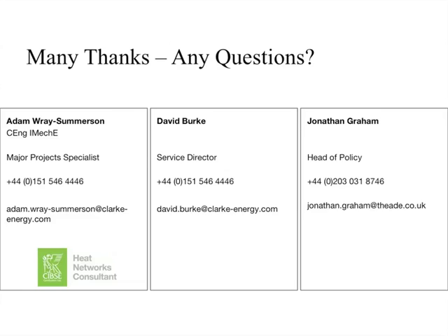That said, the GLA, Greater London Authority, have been seen to be requiring much lower emissions levels, and the question does actually refer to 150 milligrams per normal meter cube, but we've seen far lower levels than that in the Greater London area. And this drive is about existing high background NOx levels in London in particular.